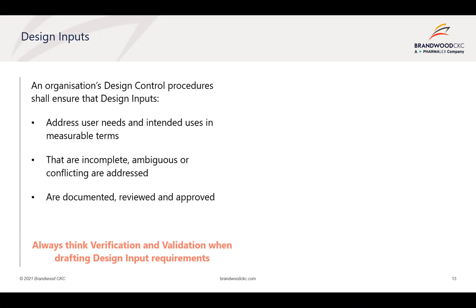So the mandatory design inputs that we consider here, from the previous slide, we have those regulatory safety and performance requirements. So considering things like the TGA's essential principles or the European general safety and performance requirements, and any other equivalent types of requirements from other jurisdictions. The other design input that's obviously critical in this case is your preliminary risk assessment. In terms of recommended design inputs, these obviously aren't mandatory, but you would need to consider any applicable harmonized or consensus standards. But like I say, they're not compulsory, but there is a clear expectation from regulatory assessors that you've considered these types of inputs. And I think the final point to be made there as well is as you're developing those design inputs, you should be considering your verification and validation, how you are actually going to map these design inputs to the outputs and how you're going to validate that against your user needs.